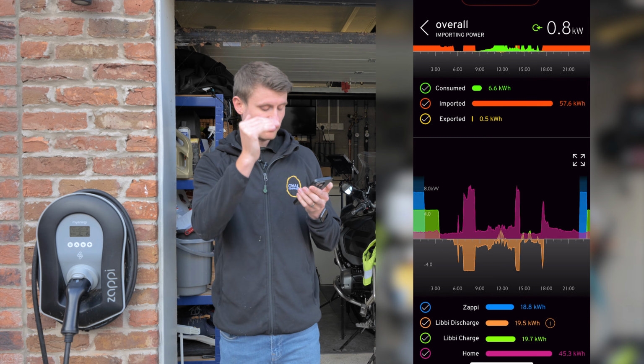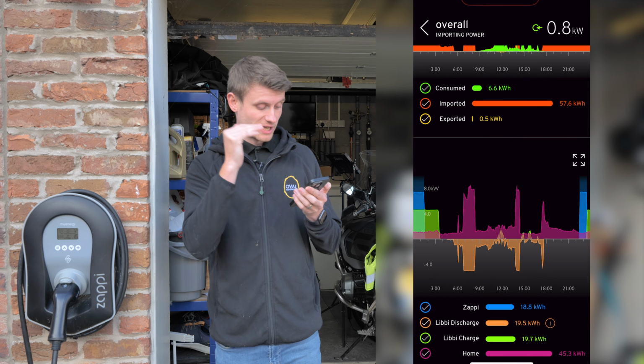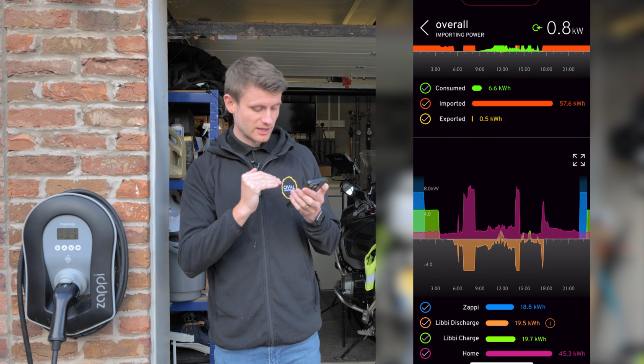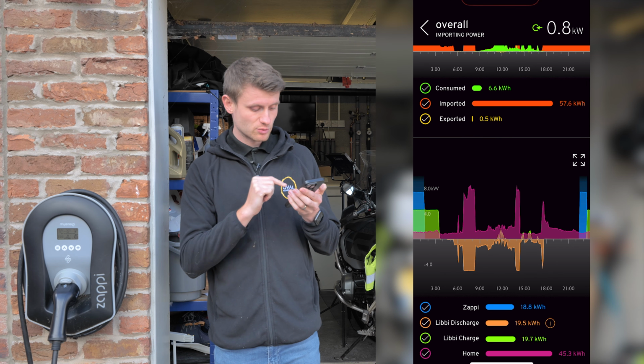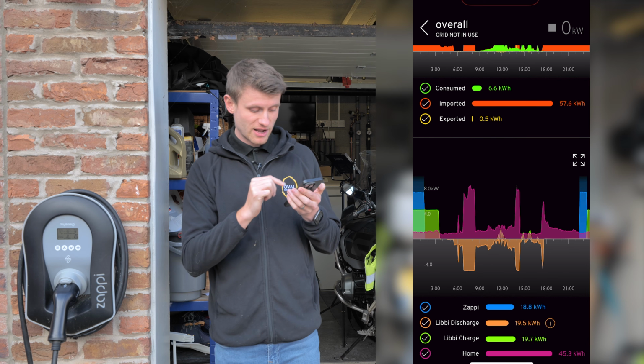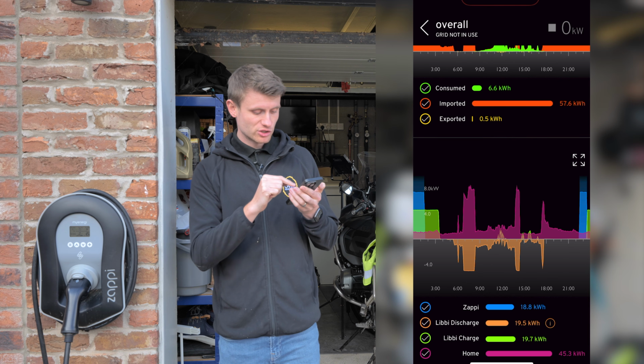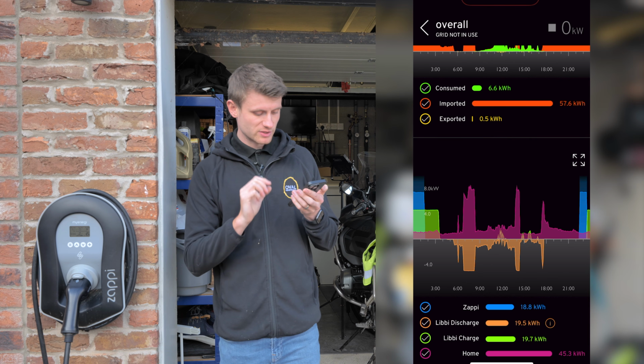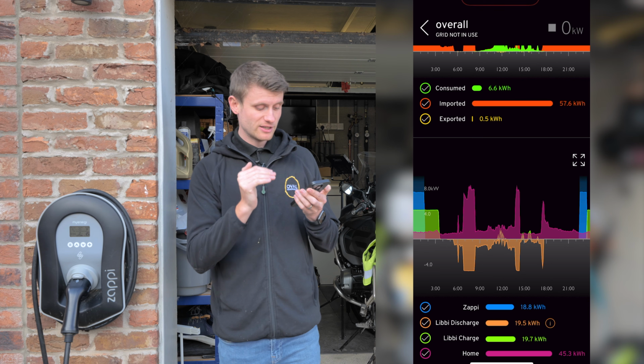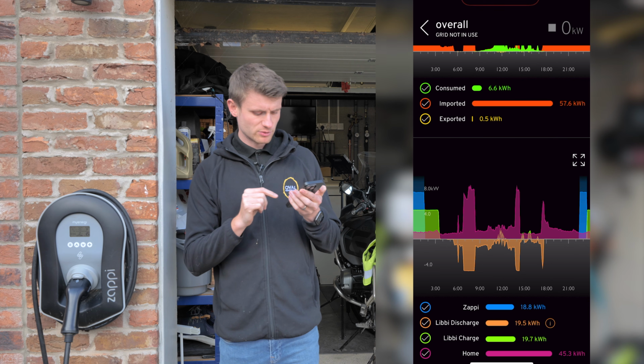And we can see above the line, on the purple colour, a really high peak there. We can also see the Libbi is maxing out below the line as well on its discharge, and similarly at around 1:30-ish we've got that spike there too. So we can see the Libbi is operating correctly, it's just trying to keep up with demand in the property.